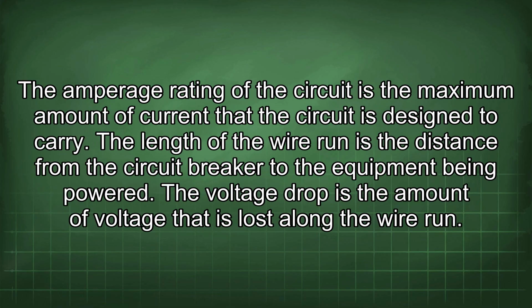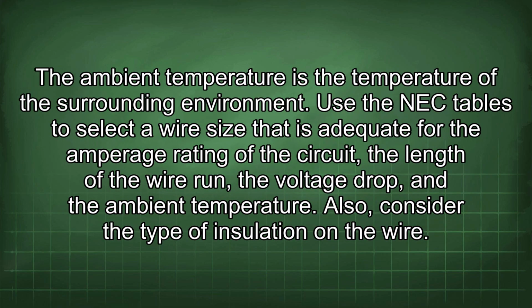The amperage rating of the circuit is the maximum amount of current that the circuit is designed to carry. The length of the wire run is the distance from the circuit breaker to the equipment being powered. The voltage drop is the amount of voltage that is lost along the wire run. The ambient temperature is the temperature of the surrounding environment. Use the NEC tables to select the wire size that is adequate for the amperage rating of the circuit, the length of the wire run, the voltage drop, and the ambient temperature.